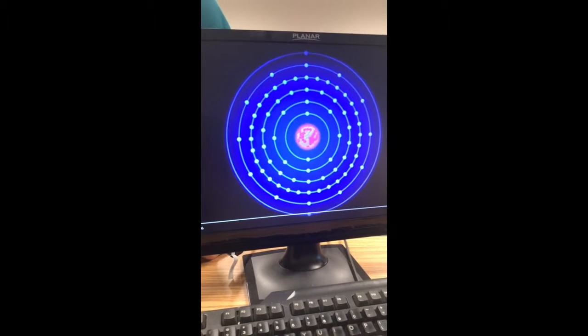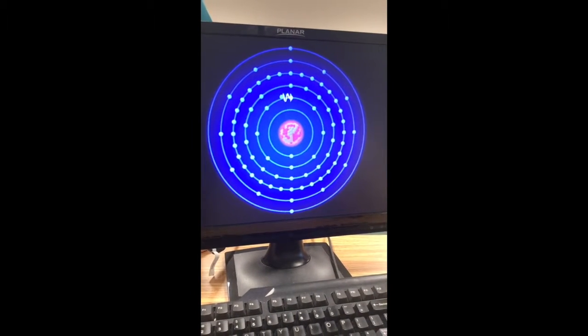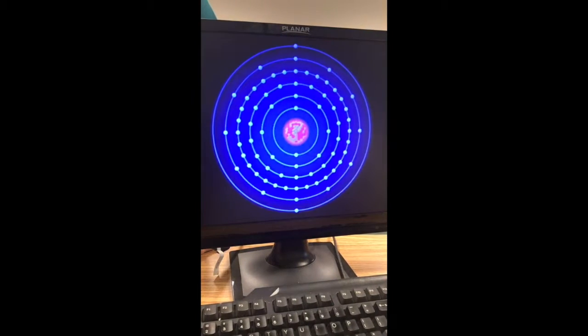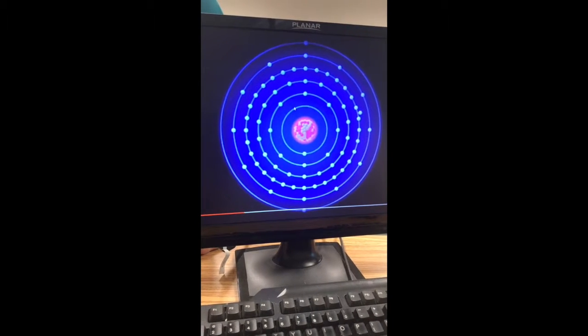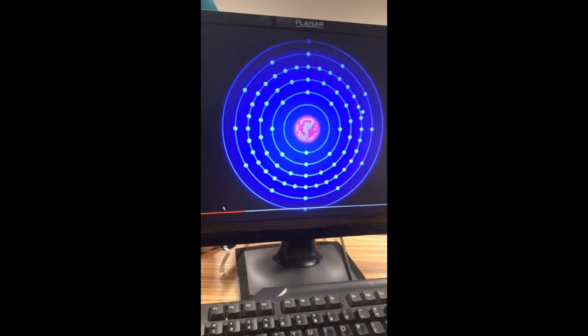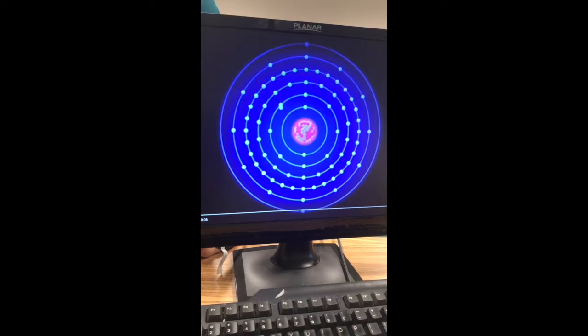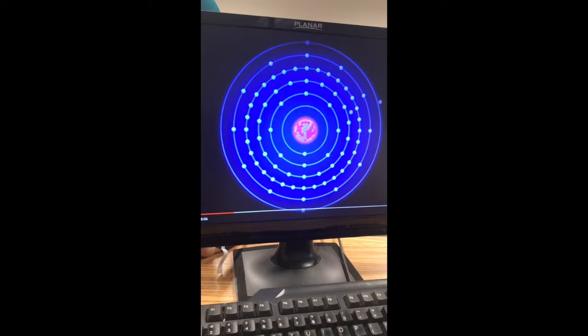Characteristic interaction, also known as K-shell X-ray production, happens when the incoming electron has an energy greater than 70 keV. This is required because the binding energy of the K-shell of the tungsten element is 69.5 keV.